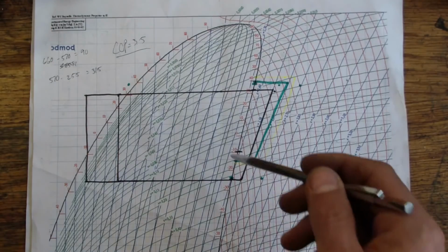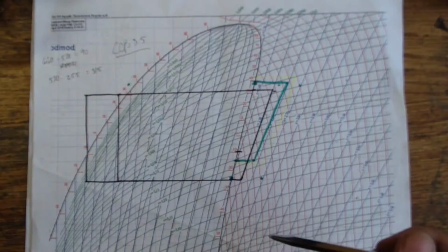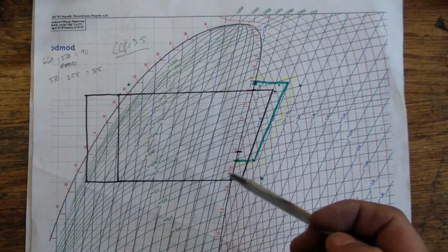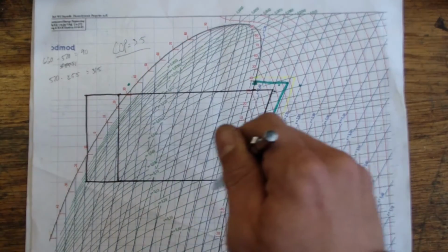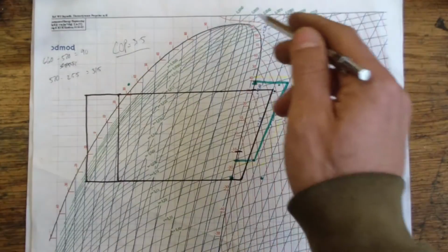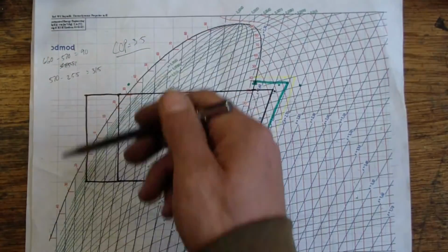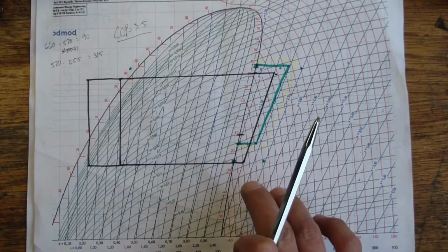So we have 4 major lines comprising this shape, and we have 4 major components in a vapor compression cycle. We have the compressor, we have the condenser, we have the throttling or the metering device, and we have the evaporator down at the bottom. So if we look at the isothermals and where they exist, and we look at the general trends of the pressure on the left side, it's cut off in this one, but we understand that as we go upward, we increase in pressure, and as we go across, we increase in enthalpy, in the heat content of the refrigerant.